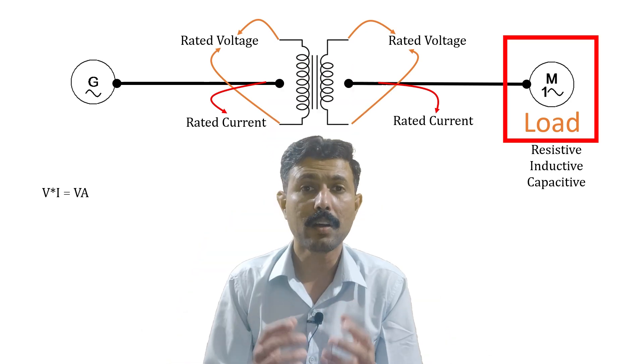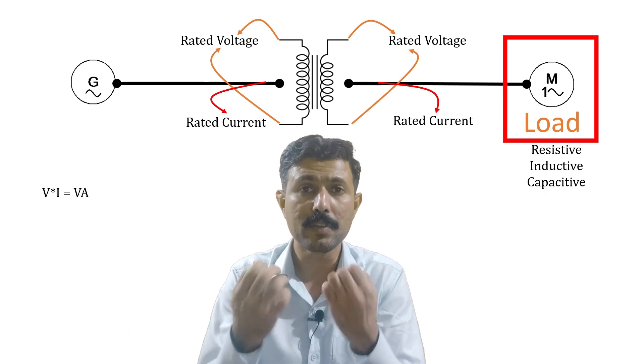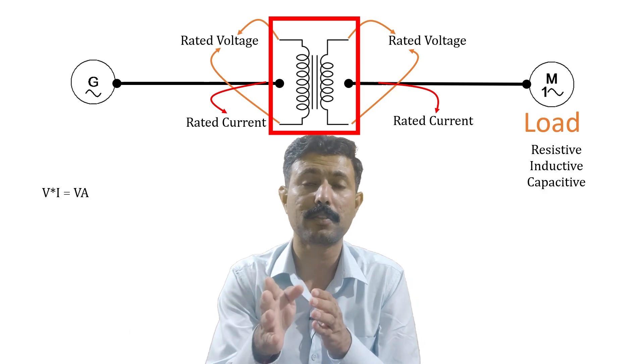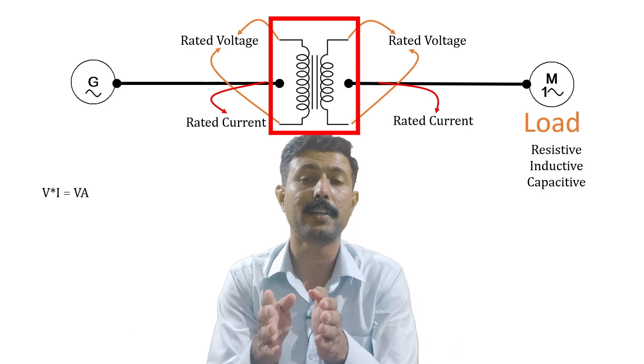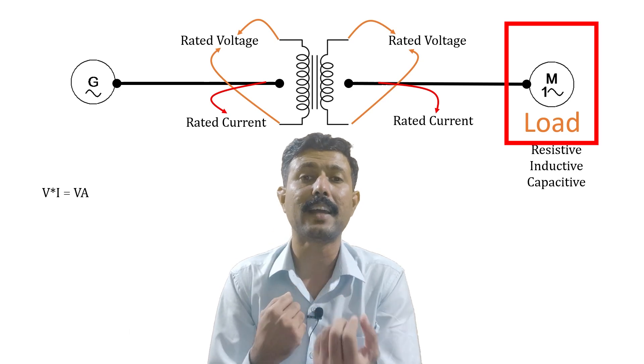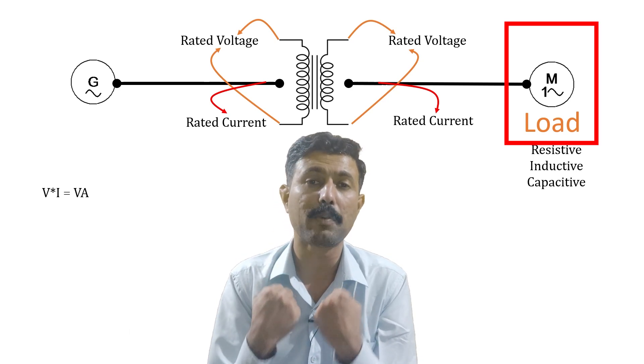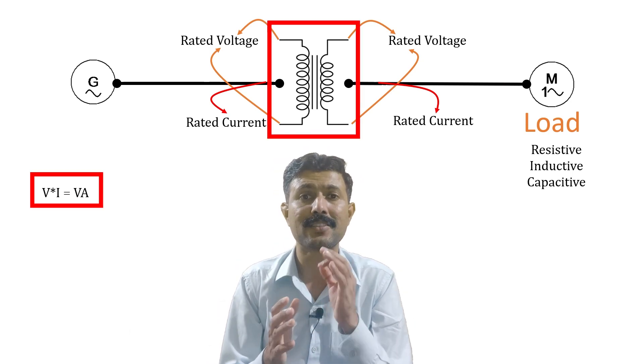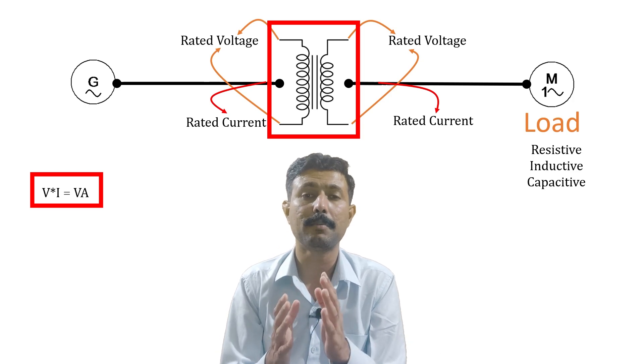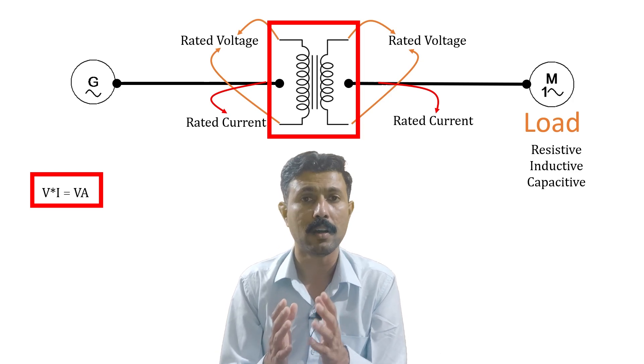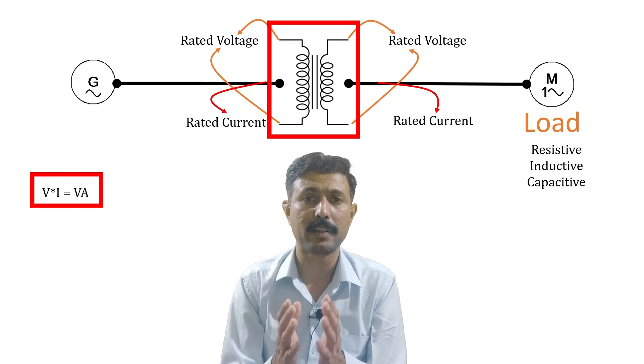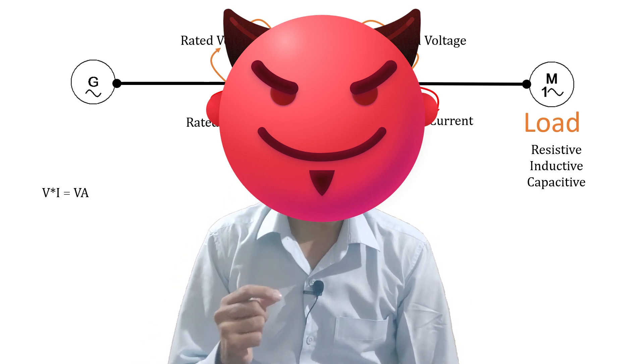That product of rated voltage and rated current is ultimately the apparent power. It is the load that decides how much active and reactive power to draw — not the transformer. The load demands a certain amount of active power and a certain amount of reactive power. That is why the transformer is rated on apparent power, which is the VA rating. This is the simplest explanation of why a transformer is rated in VA.